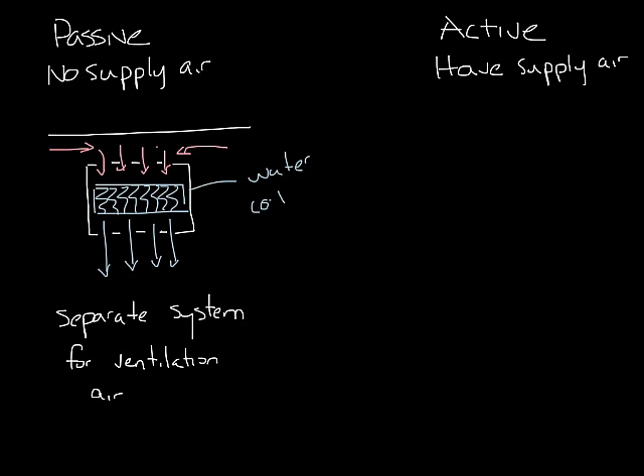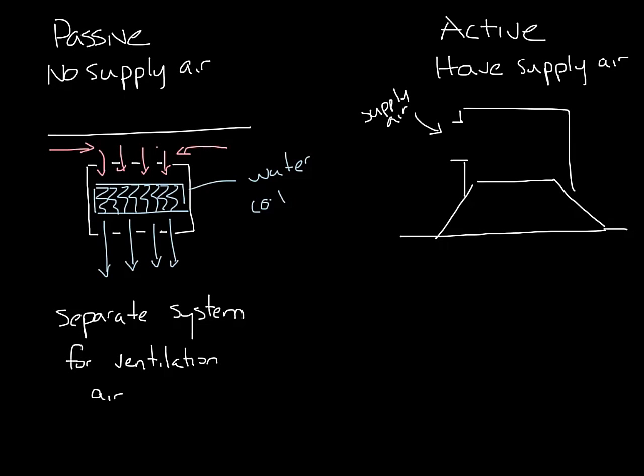Active chilled beams look a little bit like this. They mount flush with the ceiling. There's a plenum on top with a supply air inlet. And then the water coil is mounted here on the face. There are rows of nozzles along the inside of the plenum to allow air to go from the plenum into the cooling coil section of the unit.